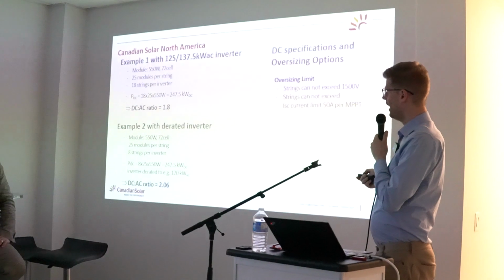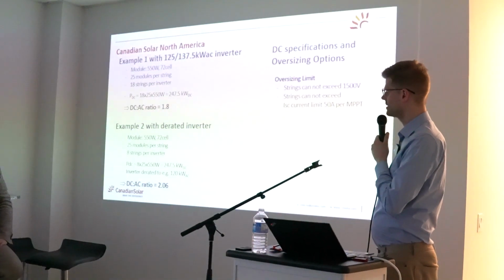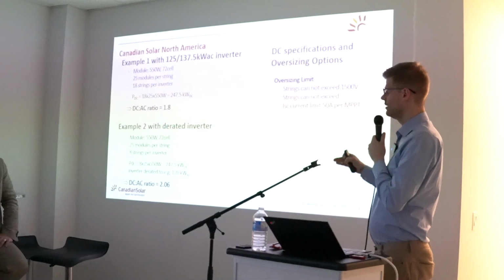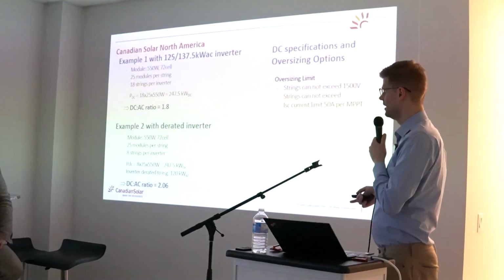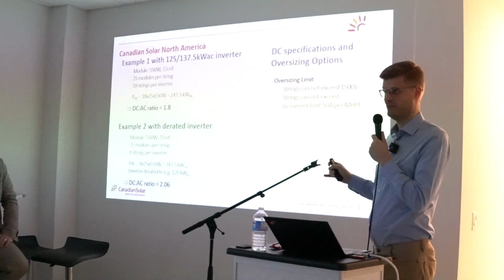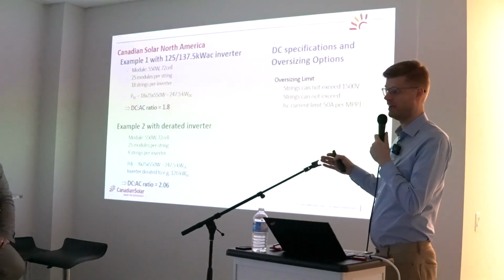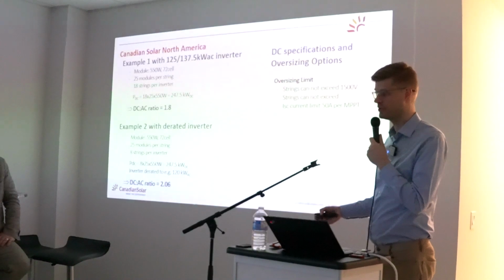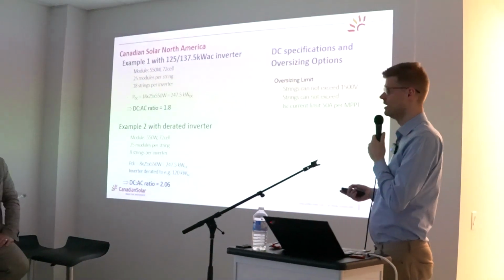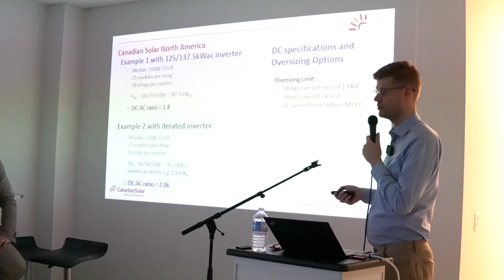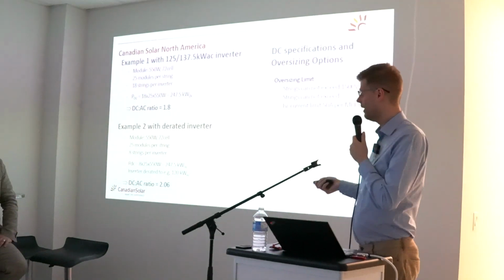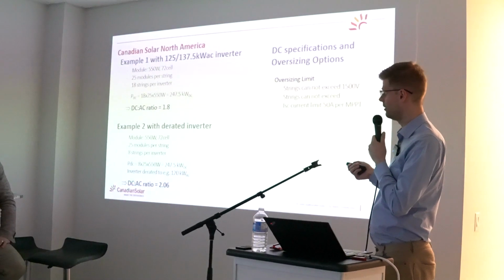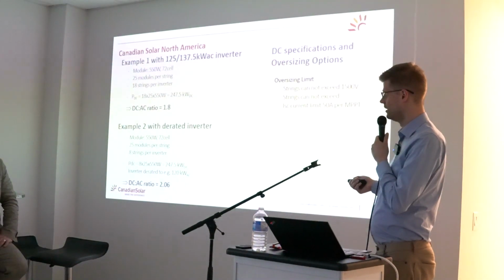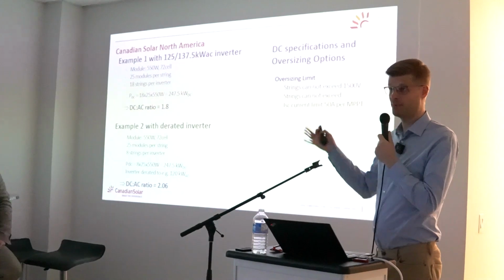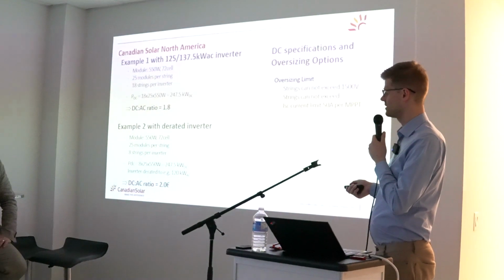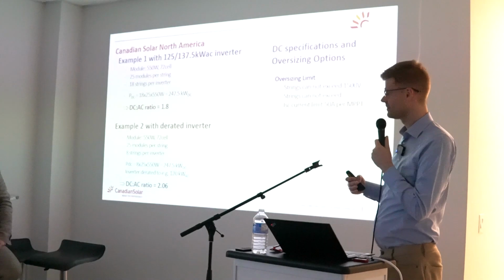I added a quick second example here, what you can do if you want to have higher DC to AC ratios. You can keep the string design exactly identical. So if the inverter is already at its maximum, because you already used all the inputs and there's no input available to you anymore, the only way of increasing your DC to AC ratio is by lowering the AC power. And that is being done by just derating the inverter from originally, let's say 137.5 to roughly 120 kilowatts or any number you like to get, in this example, to over a 2-to-1 ratio.